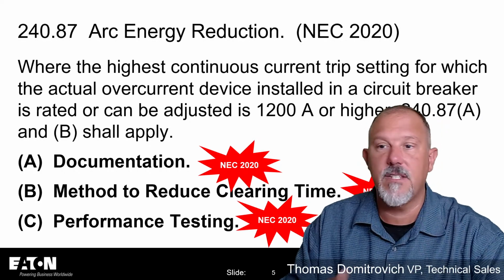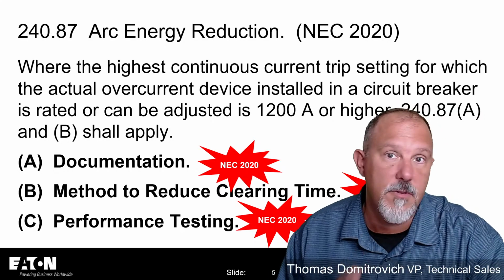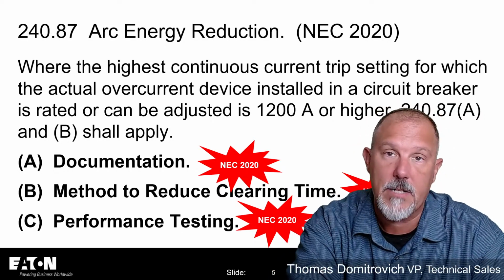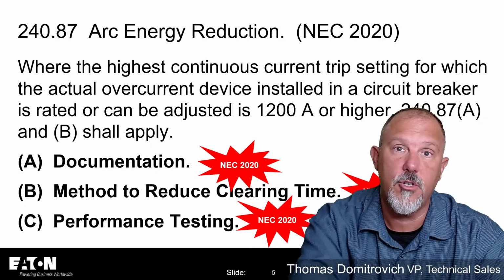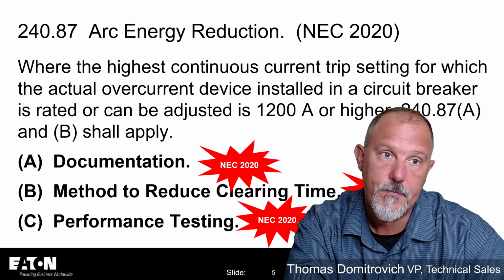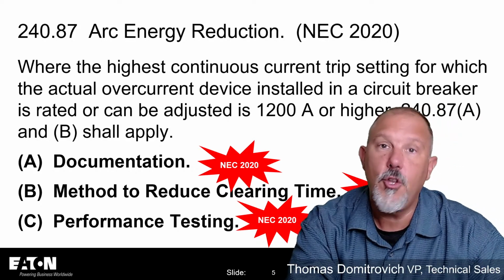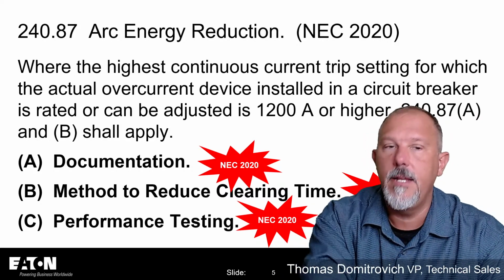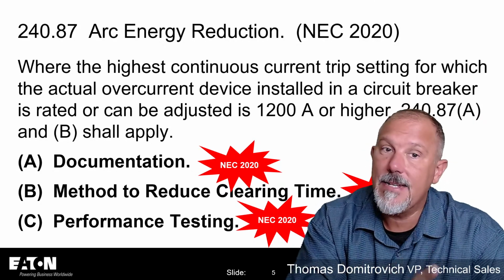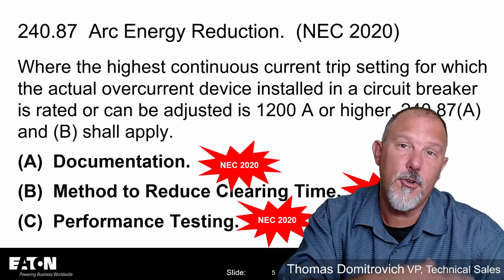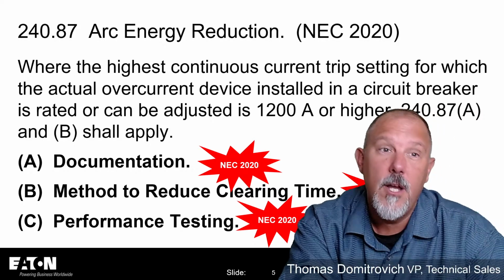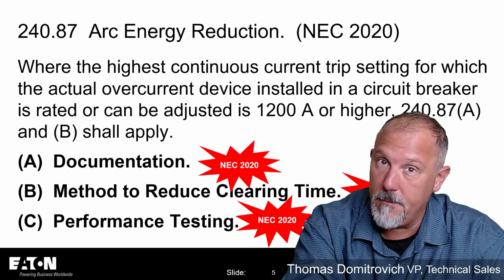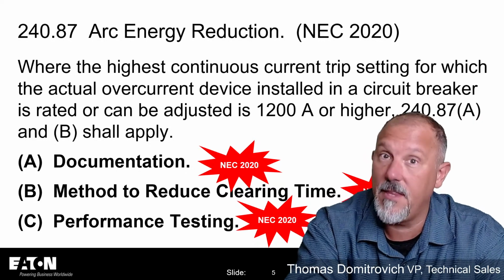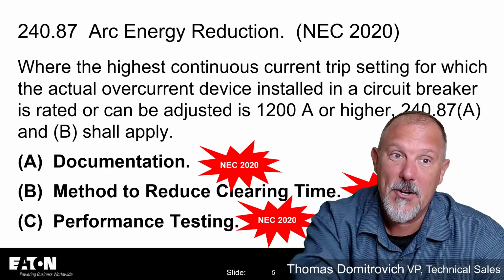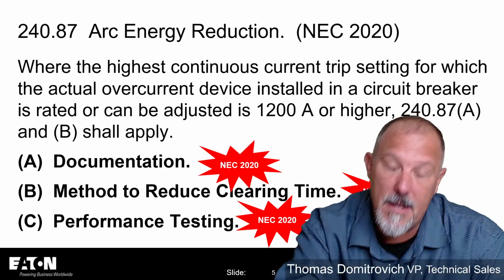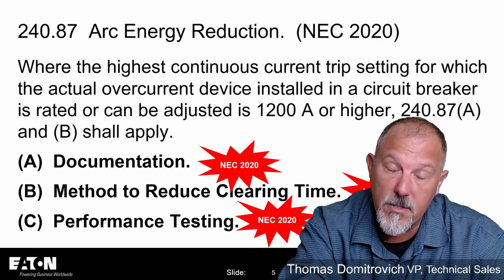If you have a plug in there that is a 1,000 amp plug and it cannot be adjusted greater than 1,200 amps, you have a good argument with the inspector to say, look, I cannot adjust that to greater than 1,200 amps. Now, they may say, well, you can take that plug out and put a 1,200 amp plug in, and they've got a valid point, but again, you're in that area where you're going to be arguing with an inspector. And remember, arguing with an inspector is like wrestling with a pig in mud, because soon enough, you'll understand that the pig enjoys it, right? So they love to argue, and that's perfectly fine because their butt's on the line with the inspection. And you've got to respect that.